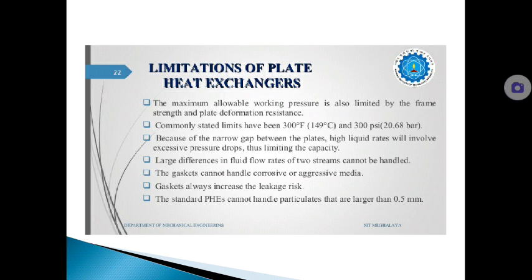Large differences in the fluid flow rates of the two streams cannot be handled. If there is a flow rate difference between these two processing fluids, it cannot be handled, so both fluids should have the same flow rate. Then, since gaskets are provided, the gasket cannot handle corrosive or aggressive media, and there is also the possibility of leakage. The standard plate heat exchanger cannot handle particulates larger than 0.5 mm. So these are the limitations of the plate heat exchanger.